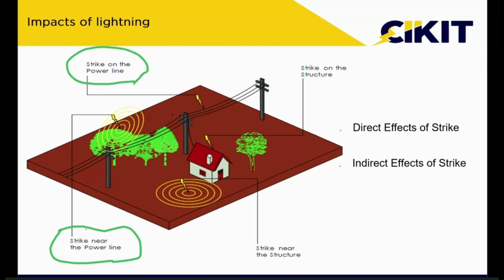Even if we have installed a lightning protection system, if we clamp its down conductor near a power line or data line, surges will get induced. Whenever current flows through any conductor, a magnetic field is produced. Even though it is a PVC insulated cable, the insulation is only for the electrical, not for the magnetic field. So if the magnetic field couples with a power line or data line, surges will get induced.